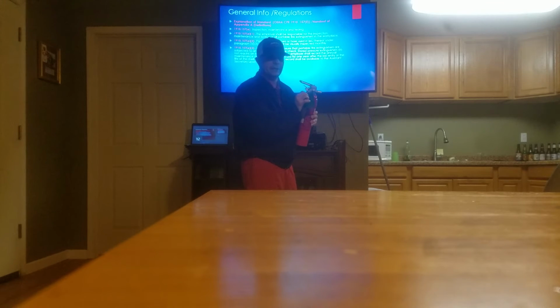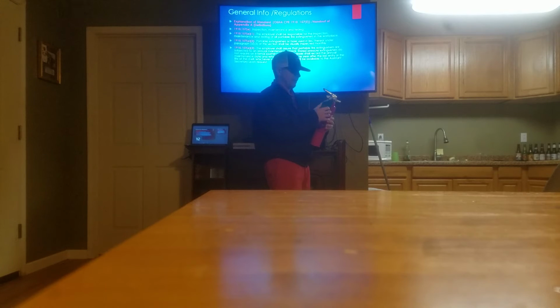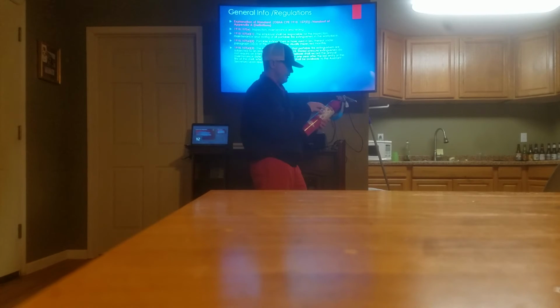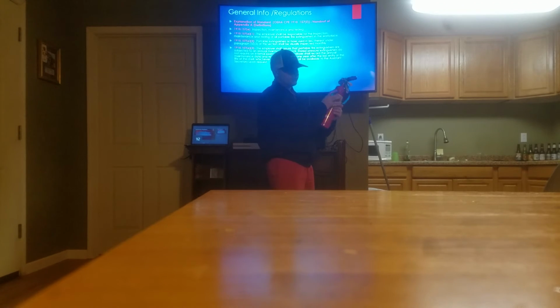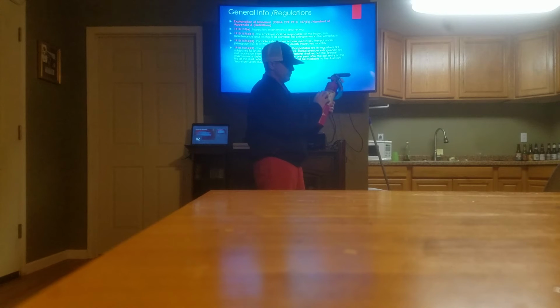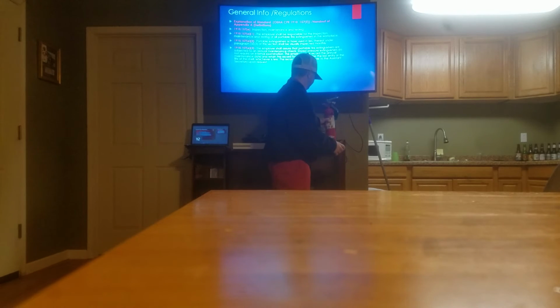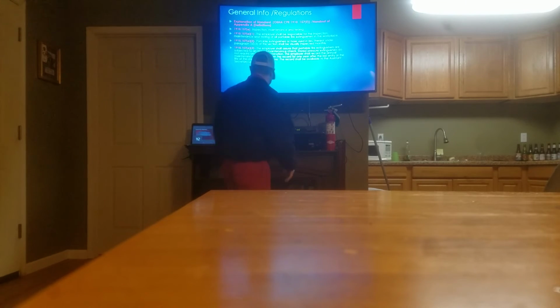You'll see these tags on a lot of fire extinguishers. This is an inspection tag for that annual inspection. And I know one thing that they're checking for in particular is the manufacturer's recommendations and the instructions right here. They're making sure nothing's covering that section, and making sure it's not damaged or anything like that. If anything's damaged on this instructions section or this front tag, this manufacturer tag, it'll fail their annual inspection.